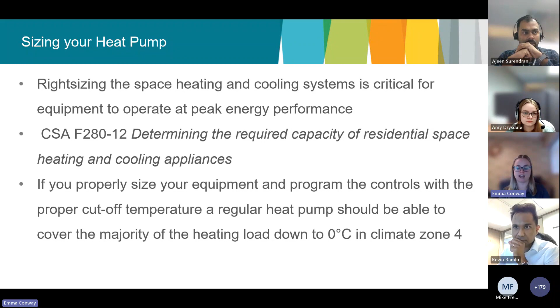If you or your homeowner are concerned about that, there are cold climate air source heat pumps. My definition, as I've heard it recently, is that this is a heat pump that can meet 90% of the heating capacity down to about -17 degrees Celsius. Some cold climate heat pumps work efficiently down to -25 degrees Celsius, maintaining a COP of 2 down to -17 degrees Celsius. This is really important to understand.